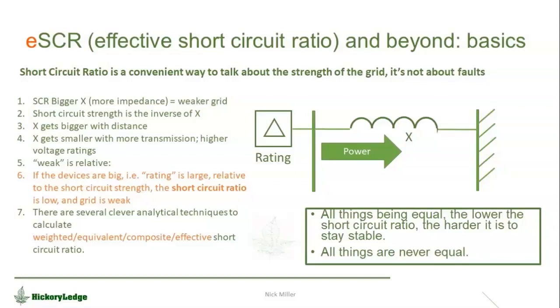So this is super basic, but quite important. The industry is spending a lot of time and energy, rightly, looking at short circuit ratios as a metric of how close the system is to running out of room, if you will, to accommodate grid following inverters. And so the takeaway box points to two things: one is that all things being equal, short circuit ratio, as it drops, makes it harder to stay stable.